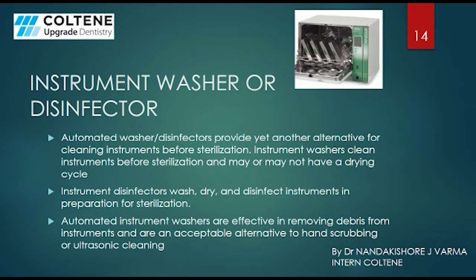What is an instrument washer or disinfector? It's an automated washer which provides yet another alternative for cleaning instruments before sterilization. They clean instruments before sterilization and may not have a drying cycle. Some of them have, but most of them do not have a drying cycle. Instrument disinfectors wash, dry, and disinfect instruments in preparation for sterilization. That is the difference between instrument washers and instrument disinfectors. Automated instrument washers are effective in removing debris from instruments and are an acceptable alternative to hand scrubbing. I have said pricking accidents can be minimized by using such equipment.